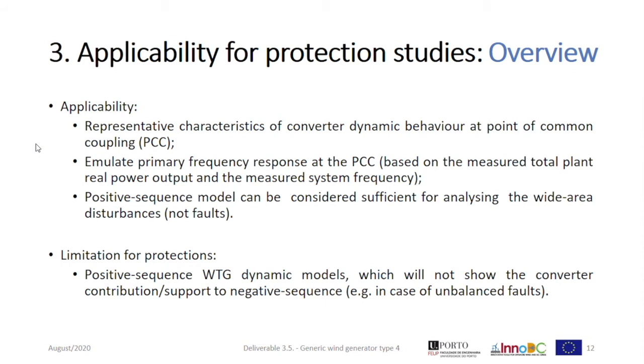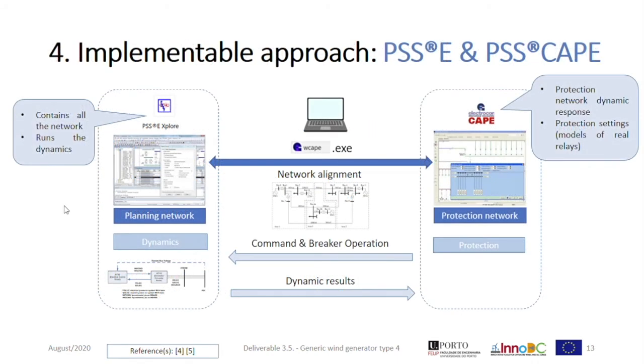Why use this model in protection studies? It provides the dynamic behaviour of the converter at the point of common coupling, including the emulation of primary frequency response, which is acceptable for wide area protection studies. However, it should be taken into account that this model only provides positive sequence dynamics, which can be a limitation for some protection studies. Up until now I have been describing the generic dynamic model of the converter. Now I will provide an implementable approach, as stated at the beginning of the presentation.